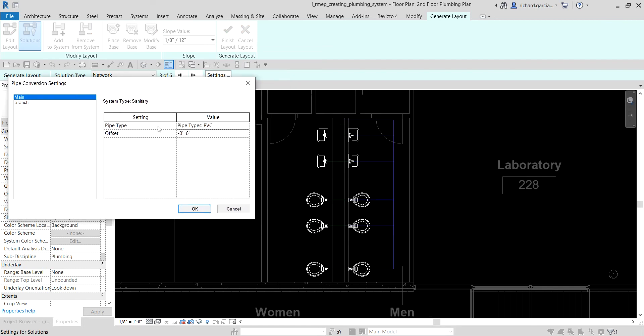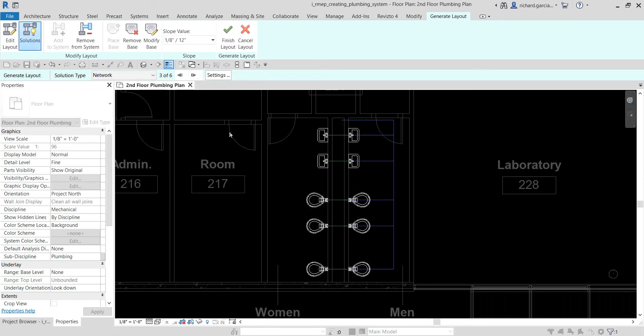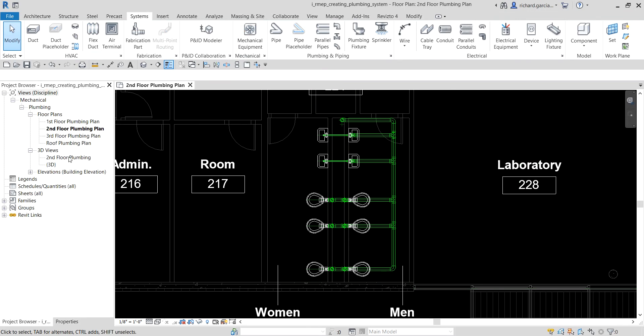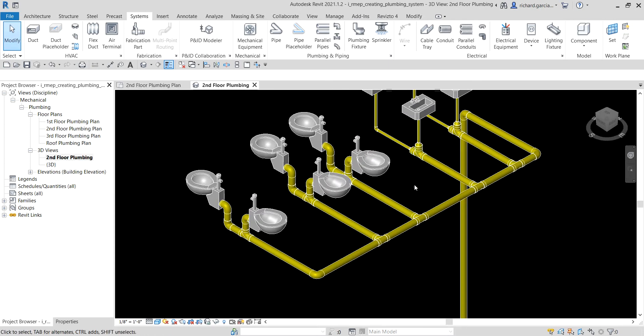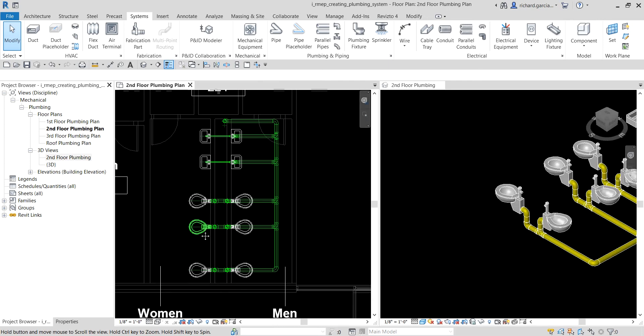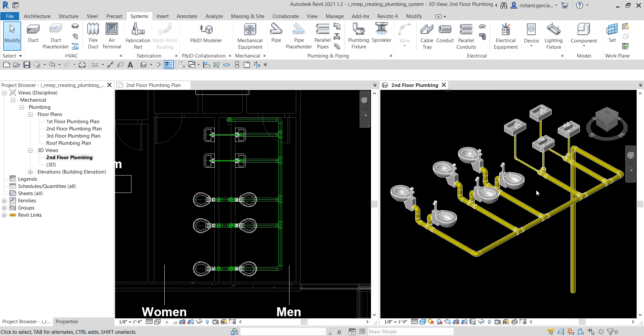In the settings, the main branch default is PVC and the offset is six inches below the main pipe — the blue pipe — while the branch pipe is shown in green. I'm going to use this offset of six inches, then finish the layout. There you go — the layout is now created automatically. I'll open the second floor plumbing 3D view and then type WT for tile window so I can see both the floor plan and the 3D view.